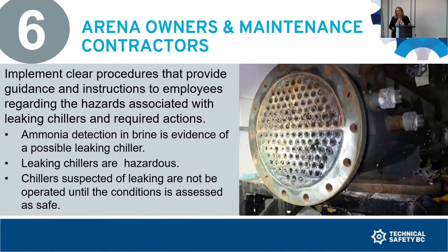As a regional business leader, the safety officers do go out, they do respond to those, they would like to know if there are incidents happening, and they will work with the teams in order to help you out. There is a zero tolerance for leaks in chillers. So if there is a leak in the chiller, pull it out of service right away. Make sure that you are doing an investigation, finding where that leak is coming from, mitigate that through maintenance and repairs. And it's at that point that you can then put it back into service once that has been done. And the asset owner and the employees need to be fully involved. They cannot discharge the duty down to the contractor. So they need to be involved all the way along through that process.